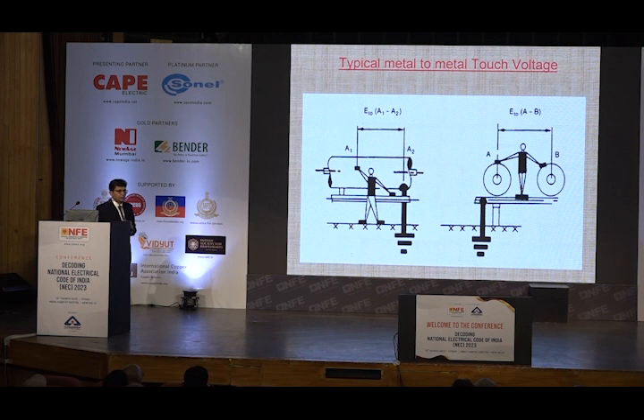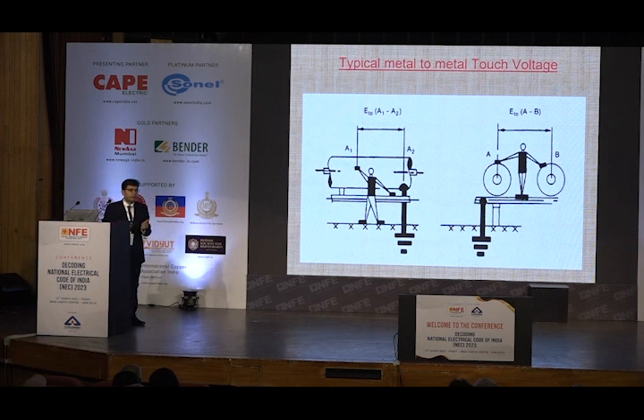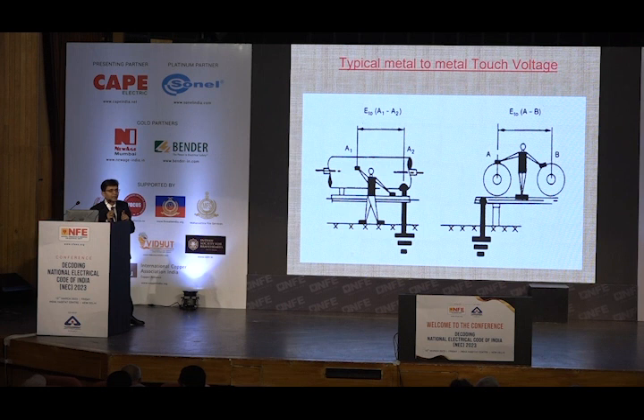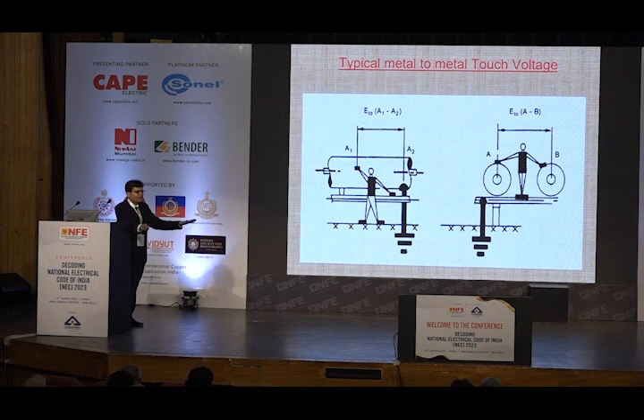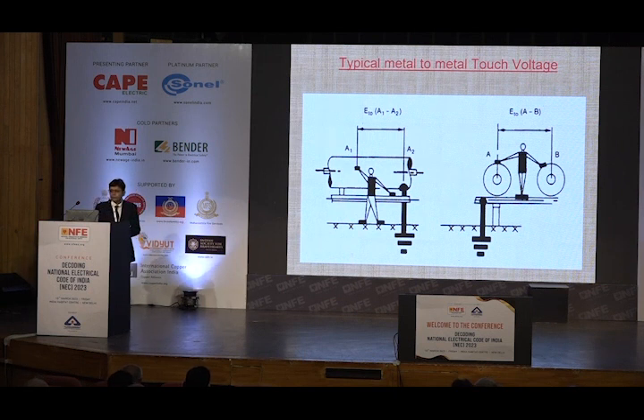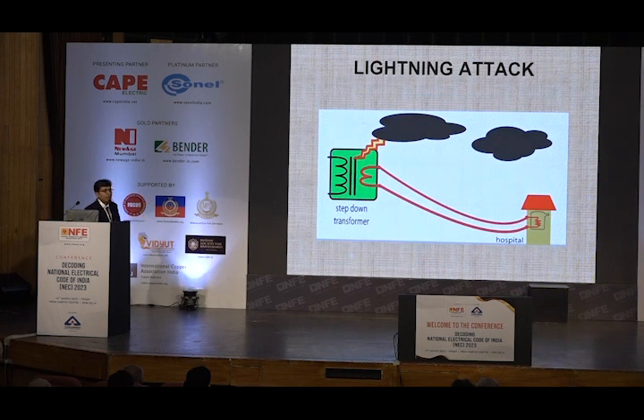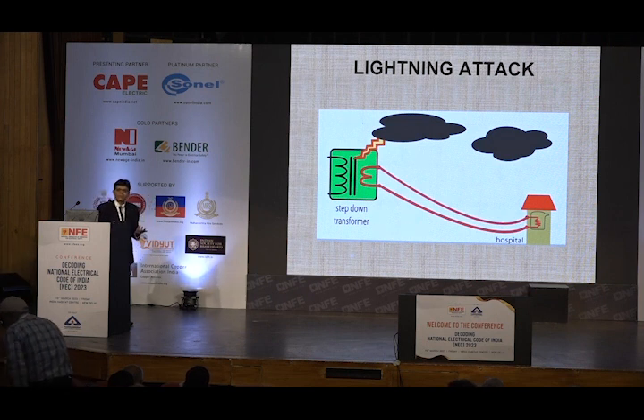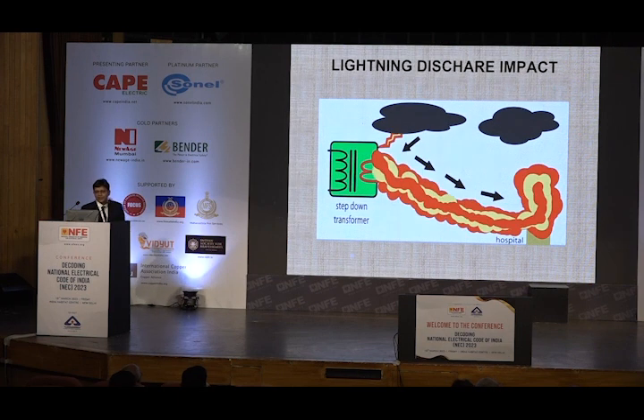Sometimes within your systems, when you start touching two metallic objects in the same premises, be careful about metal to metal touch voltage, and that can be avoided with proper bonding and equipotential systems. Otherwise there will be a potential difference between the two hands touching that metallic part, and you will get a shock for sure. At point number 7, I have talked about external unwanted energy. It is depicted by that picture. When lightning strikes your equipment, you need some systems to protect it, and that can be protected by proper and adequate earthing.